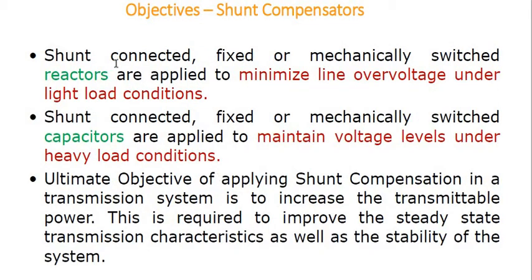Shunt connected fixed or mechanically switched reactors are applied to minimize line overvoltage under light load conditions. Shunt connected fixed or mechanically switched capacitors are applied to maintain voltage levels under heavy load conditions.